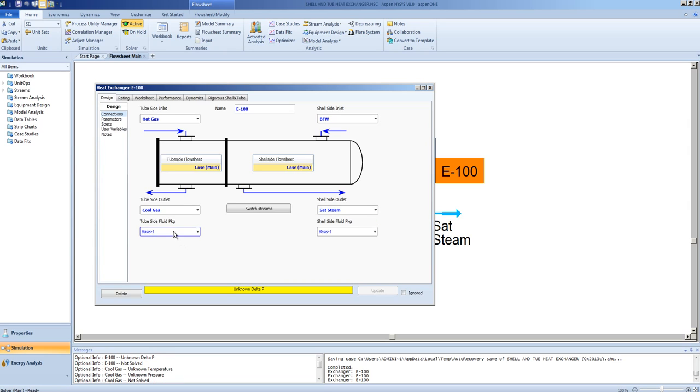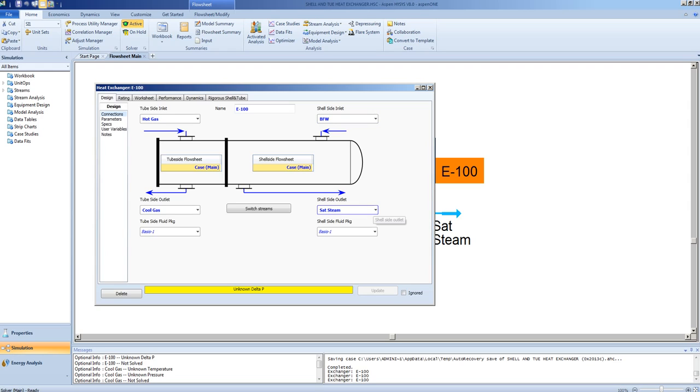Note, for either side of the exchanger, you can specify the fluid package that is applicable. This is useful for when there are systems that may be using components that are compatible with one fluid package on the tube side, and another fluid package on the shell side. An example of this may be using glycol as a coolant for hot oil. The oil may use the Peng Robinson package, and the glycol would use the glycol package on this side.